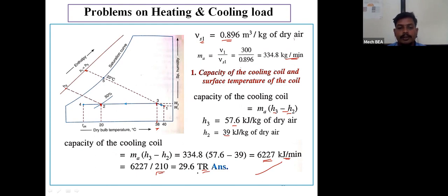I will get the value or capacity of cooling coil in terms of ton of refrigeration. Now after calculation of capacity of cooling coil, we have to find out the value of surface temperature. As we are using the cooling coil, the surface temperature of cooling coil will be less than the outlet air or required condition. So here I know that point number 4 will have a lower value as compared to 20 degrees centigrade.